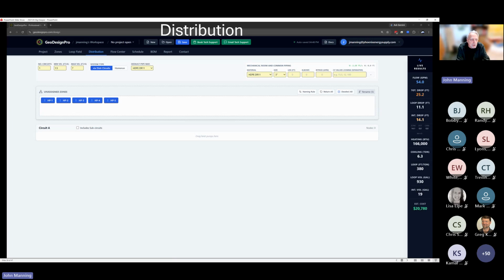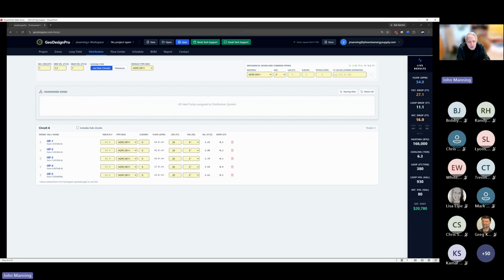Let's move on to the distribution tab. This is where you get to model all the interior piping of a system. And here we've got our 5 heat pumps that show up in an unassigned box, but by simply dragging and dropping those into a circuit box, we have now created a distribution system. And you can identify what room the heat pump's located in. You can change the order in which these are being fed simply by a drag and drop function with your mouse. You stipulate what kind of pipe material, how many elbows.